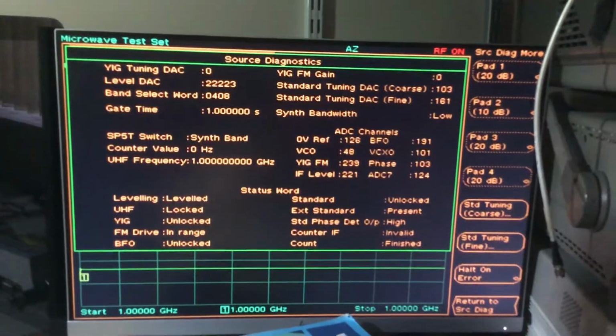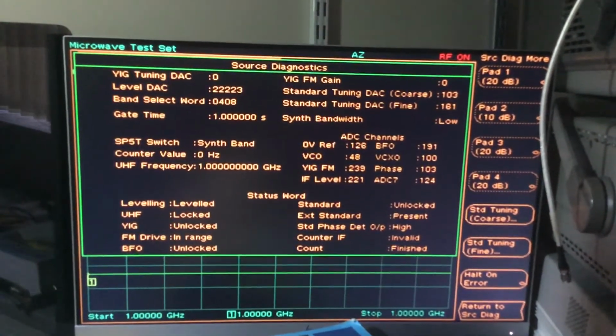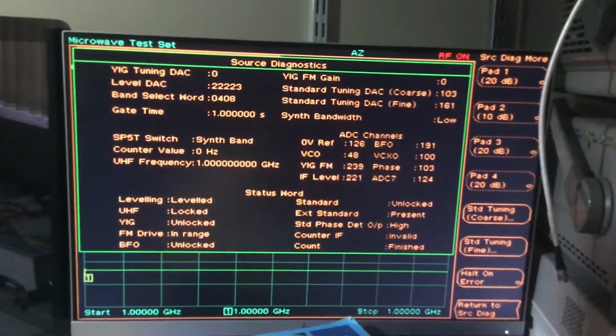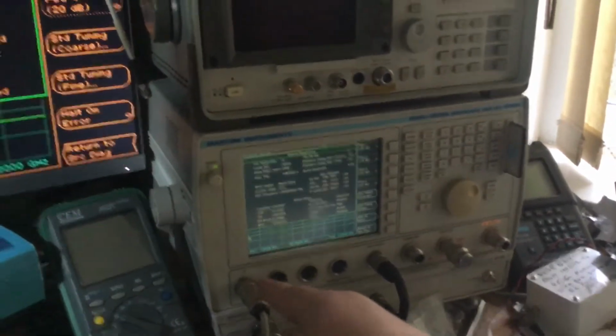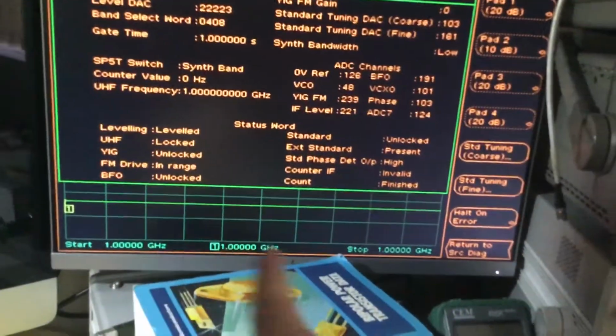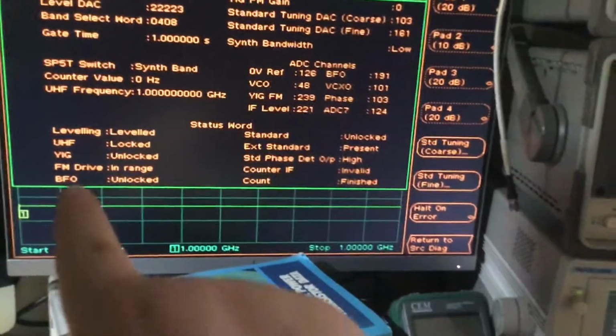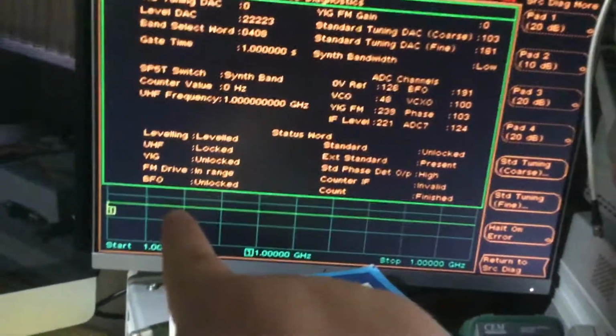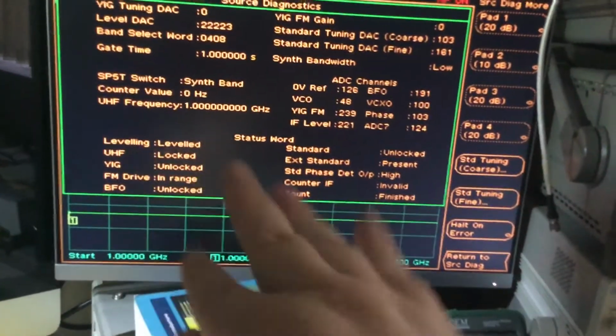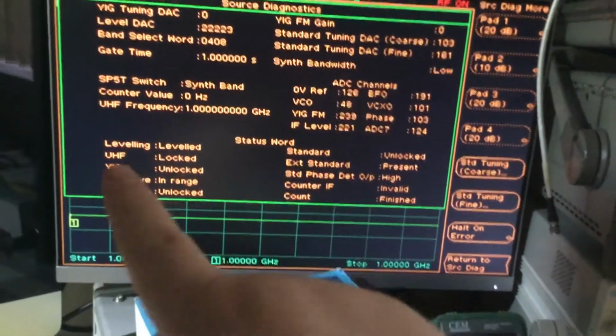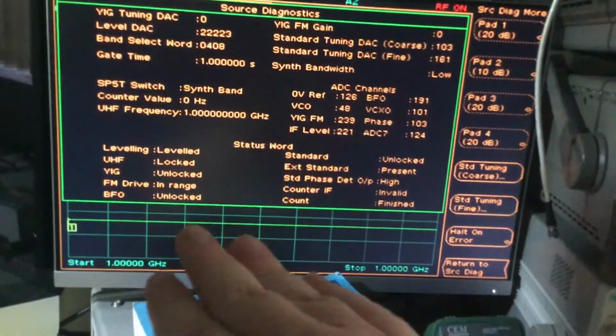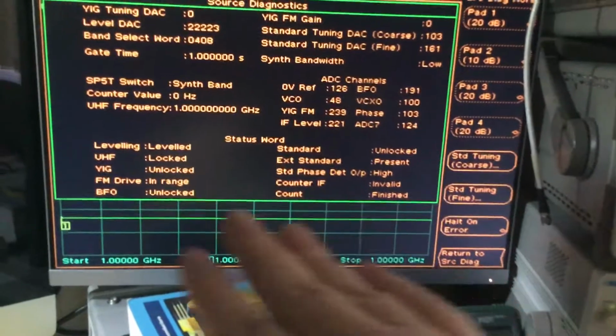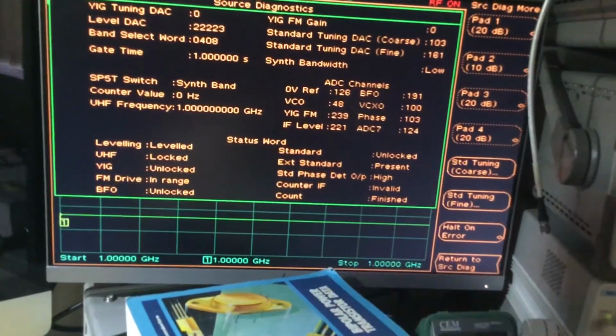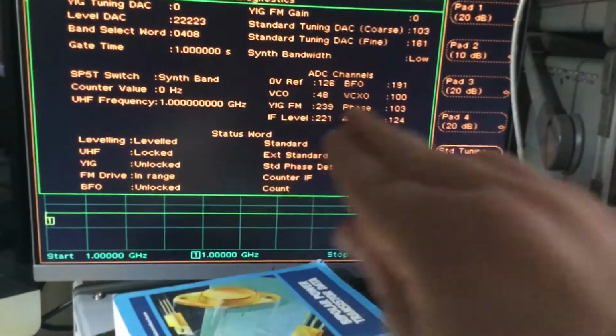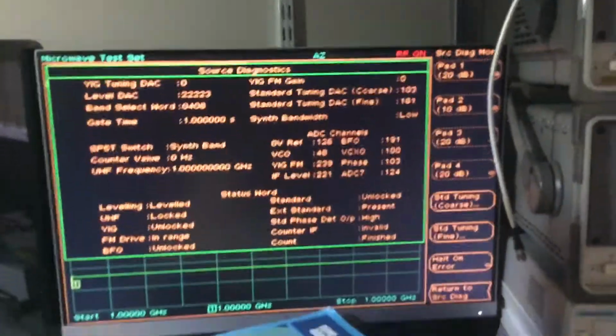So obviously if you didn't calibrate the instrument properly, it would be like when you use it in scalar mode and you have the sensor connected on the RF output to the scalar, and you're sweeping from 10 megahertz say to 20 gigahertz, instead of it being a nice flat line like you've got there at the bottom, which you can just see, it should look something like that. It will be like a plateau of mountains. It'll be going up and down all over the place because it can't keep the level in lock, and at different frequencies the level will be higher than others because of the way that the RF circuits perform at those different frequencies, so it'll be all over the place and out of calibration.